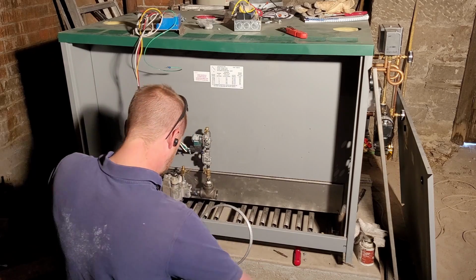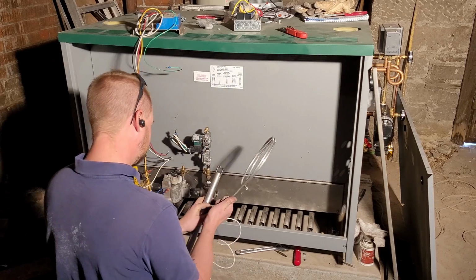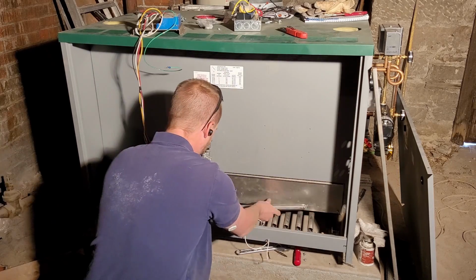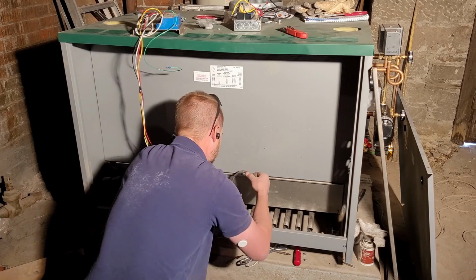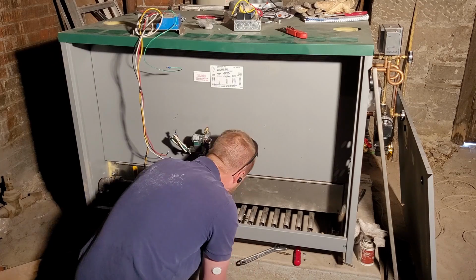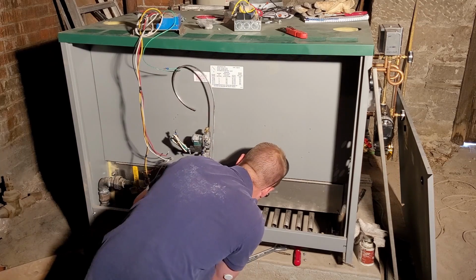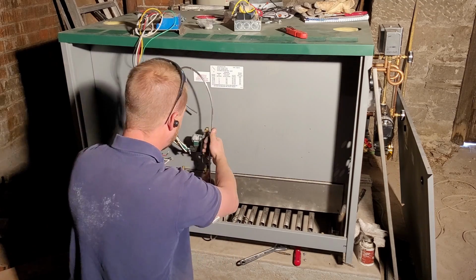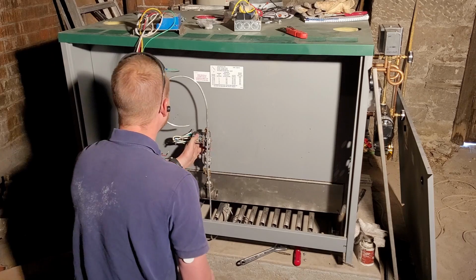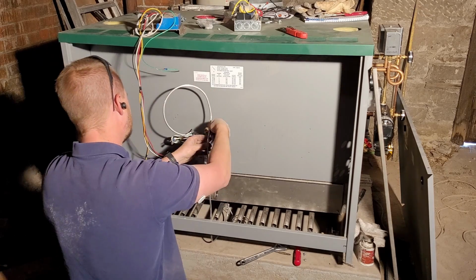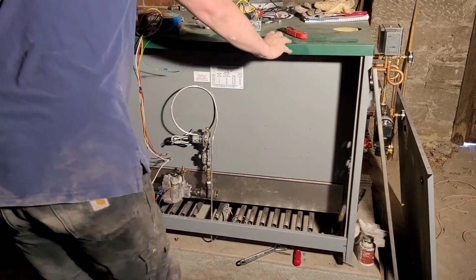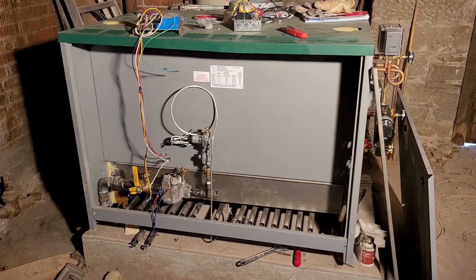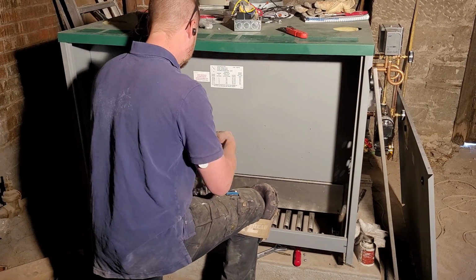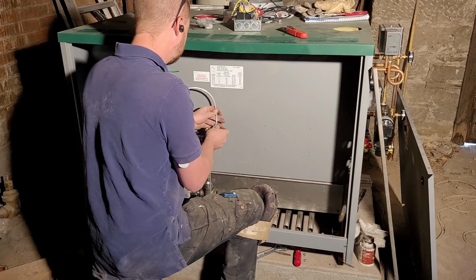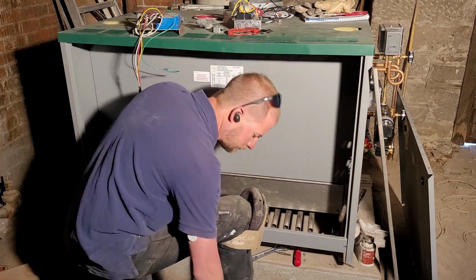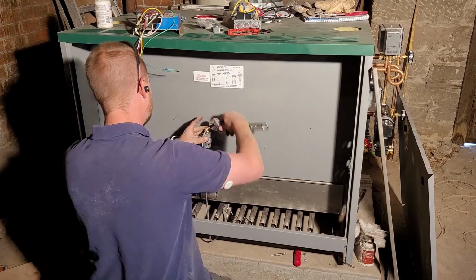So one thing I did want to point out is on the newer equipment, a lot of times on older boilers, what was the standard for a long time was what was called a thermocouple. And you would have a thermocouple sit in the pilot flame, and it was two dissimilar types of metal that when you heat them up, it actually creates a little voltage. So you would use that voltage to power a very small solenoid in the gas valve, and that would do two things. It would keep the pilot lit, it would keep the gas valve to the pilot open, and then it would also move a little pin out of the way to allow the main valve to open. So mechanically, the main gas valve couldn't open if that pin was in the way.